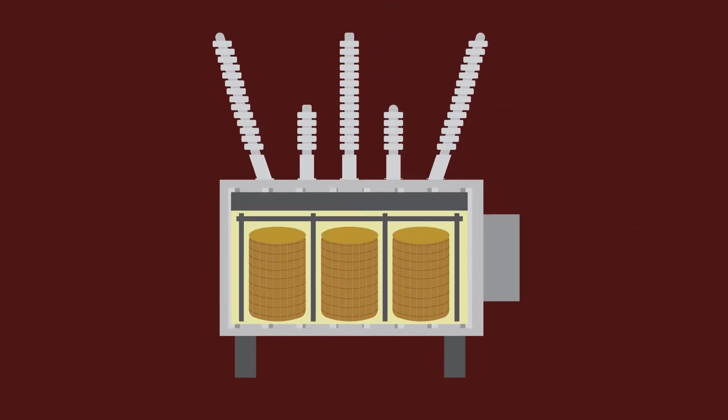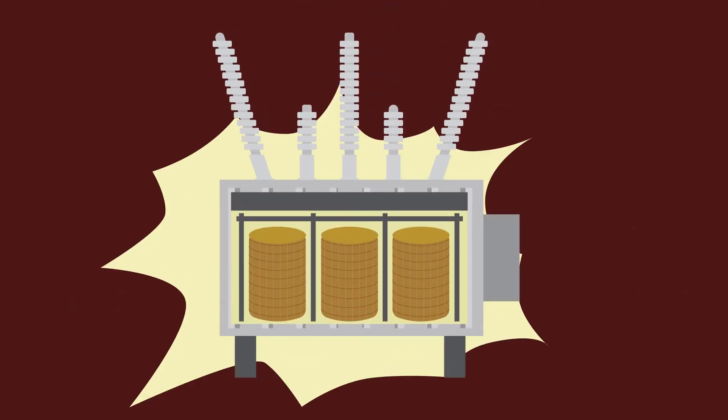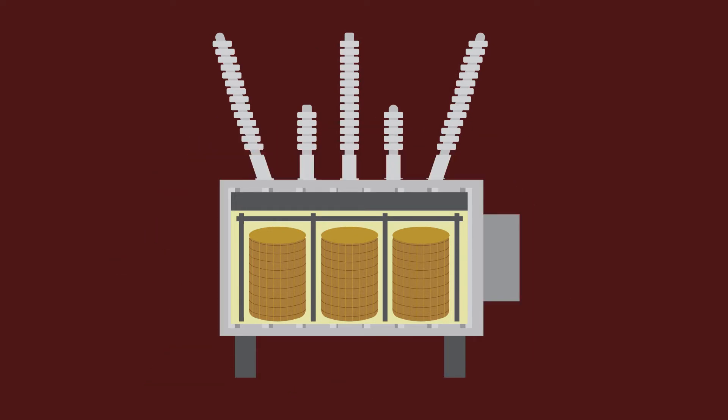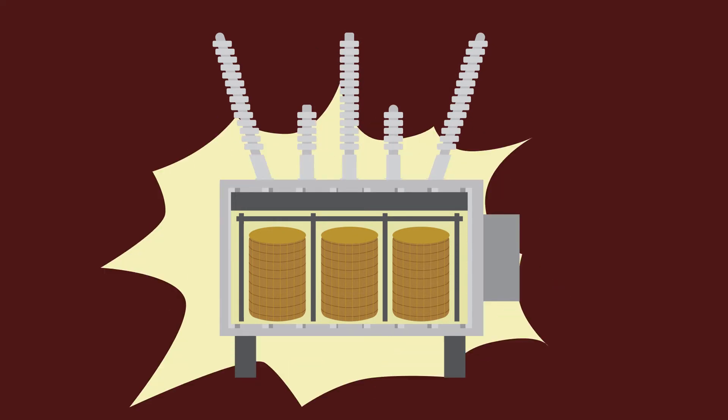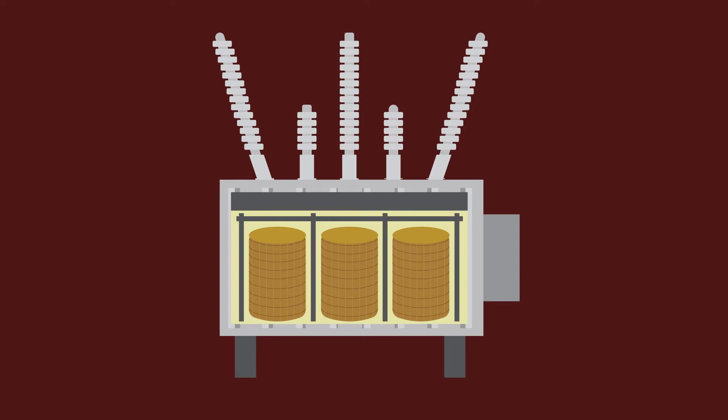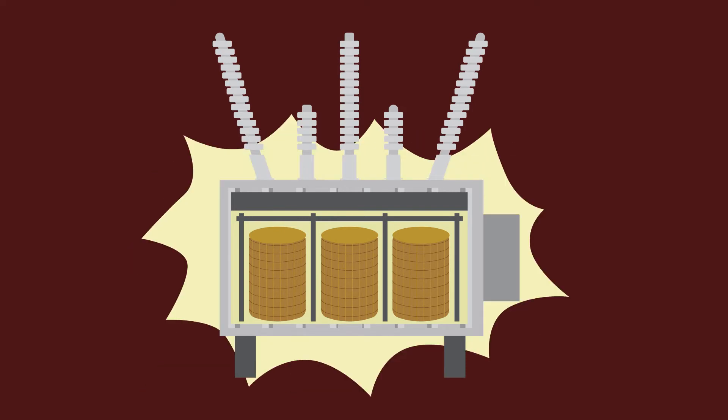When a through fault occurs, an excessive amount of current is induced within the transformer's windings. This current can be several times the transformer's rated current.